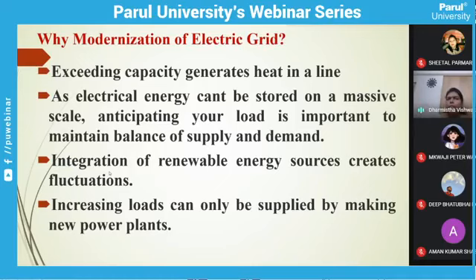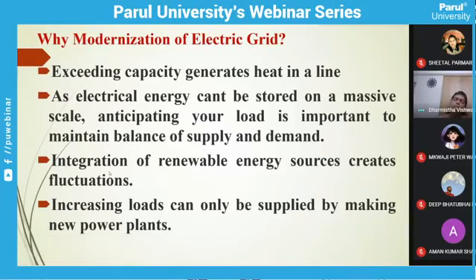To avoid this system failure, the amount of power flowing in the transmission line must be below the line's capacity. We cannot go to the maximum limit where 100% power and 100% demand are available simultaneously; the demand must always be kept less than the capacity of the transmission line. If we exceed the capacity beyond the limit, heat will be generated on that line, which will cause system failure, create instability, or lead to phase or voltage fluctuation.